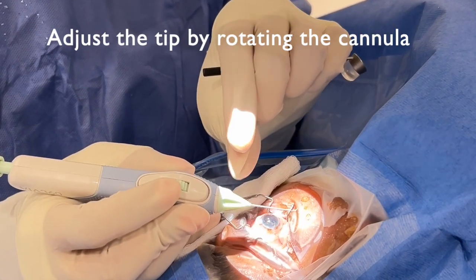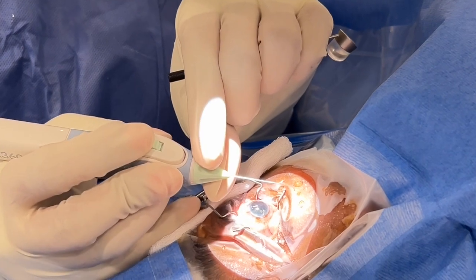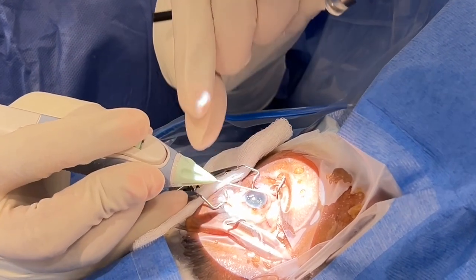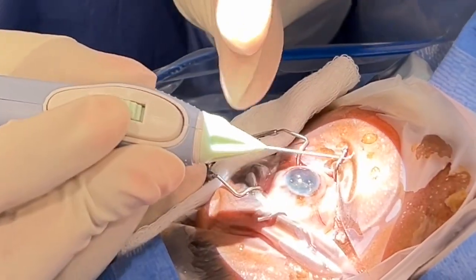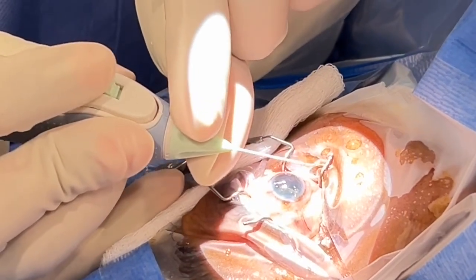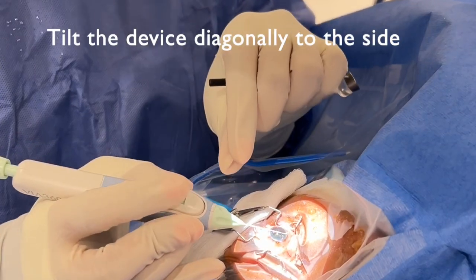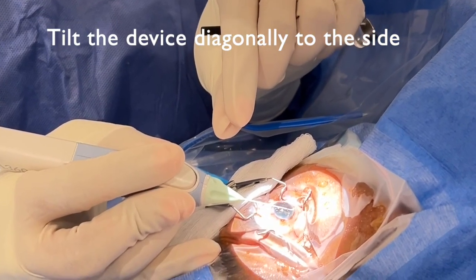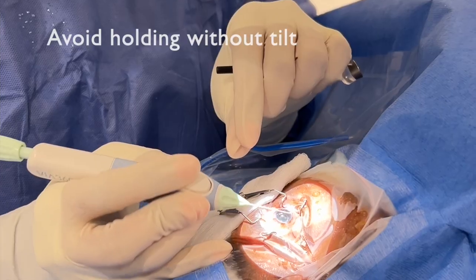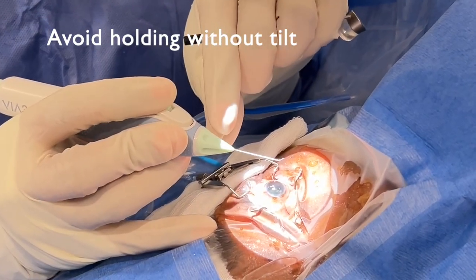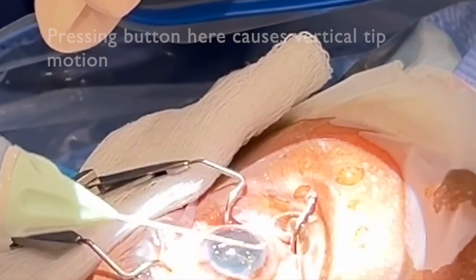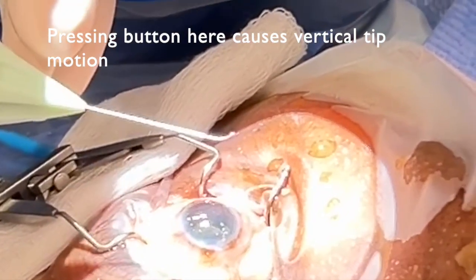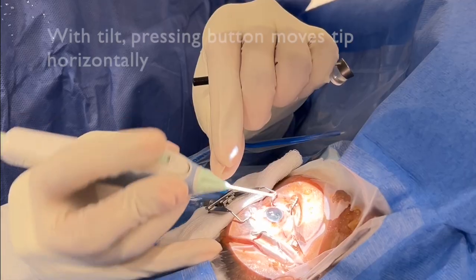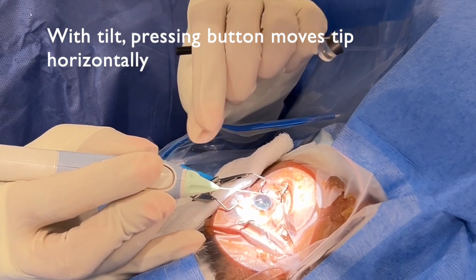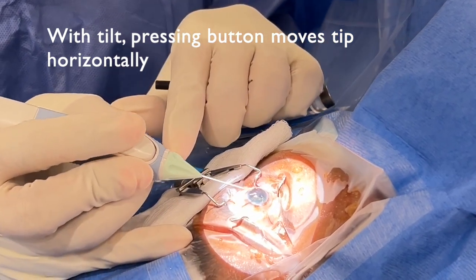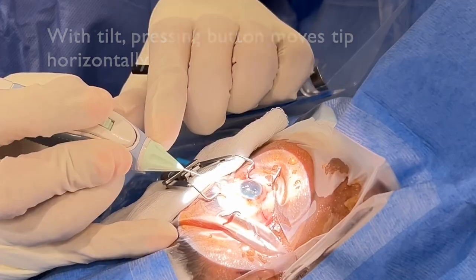Adjust the tip of the handpiece by rotating the cannula to an angle that feels comfortable in your hands. I like to have mine bevel up about 20 degrees. Next, tilt the device diagonally to the side. You want to avoid holding it without a tilt because pressing the button here causes vertical tip motion up and down. With a diagonal tilt, pressing the button moves the tip horizontally along the wall of Schlemm's canal.